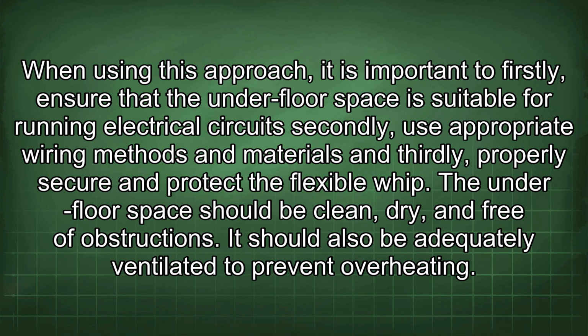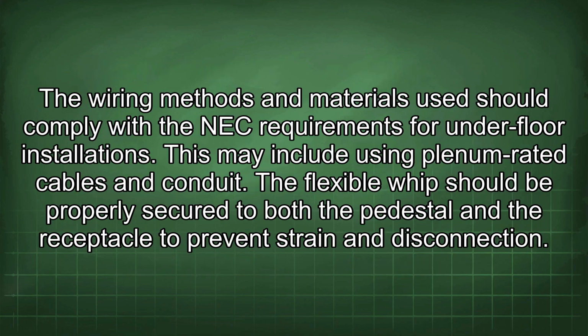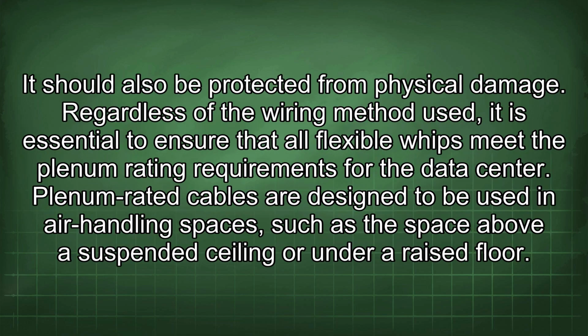The underfloor space should be clean, dry, and free of obstructions. It should also be adequately ventilated to prevent overheating. The wiring methods and materials used should comply with the NEC requirements for underfloor installations. This may include using plenum-rated cables and conduit. The flexible whip should be properly secured to both the pedestal and the receptacle to prevent strain and disconnection. It should also be protected from physical damage.